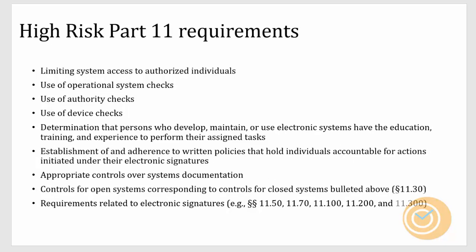So here are some of the high risk Part 11 requirements. You need to make sure that the computer software you are using for calibration and asset management addresses each one of them in a very detailed way. And the system should have controls in place so that only authorized individuals are able to access the systems.